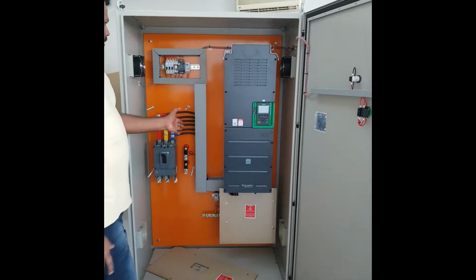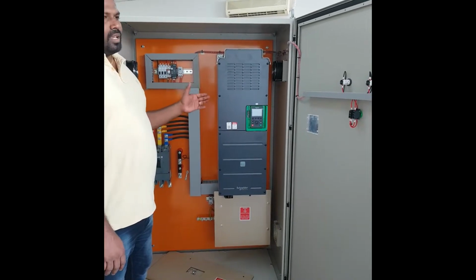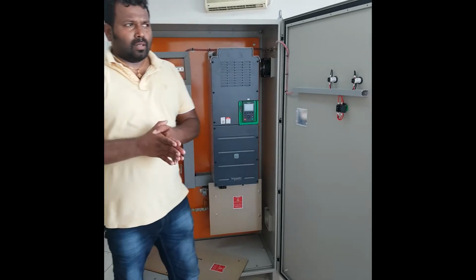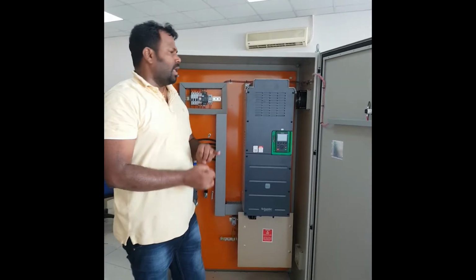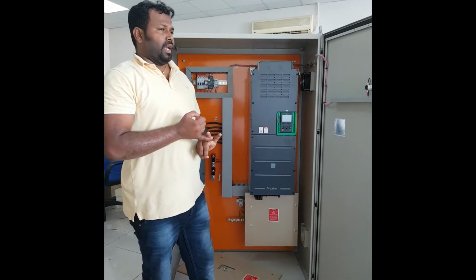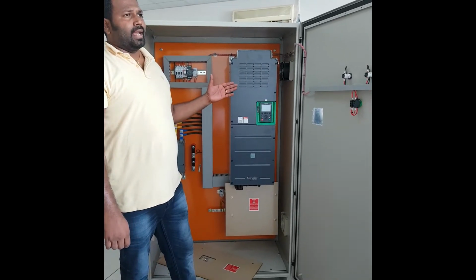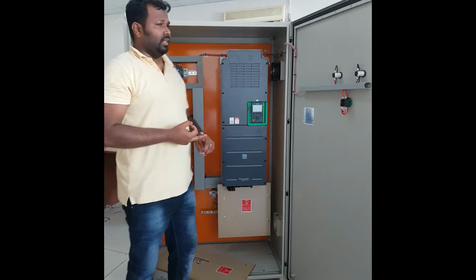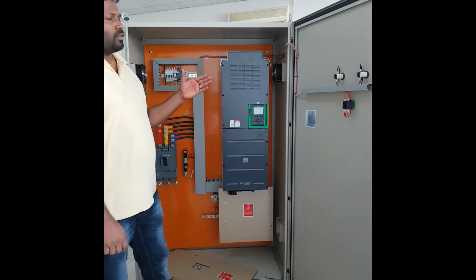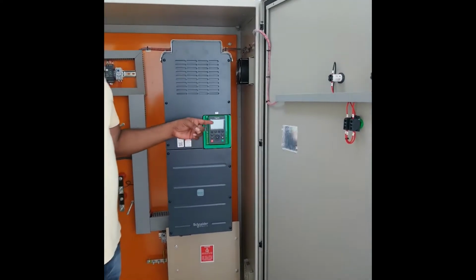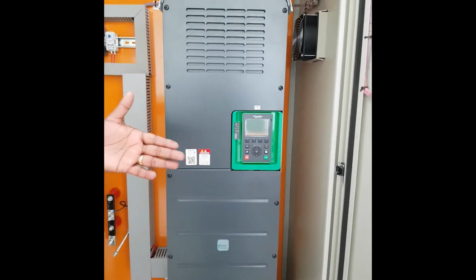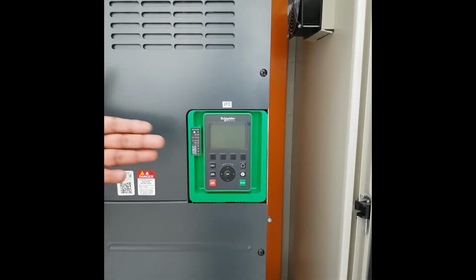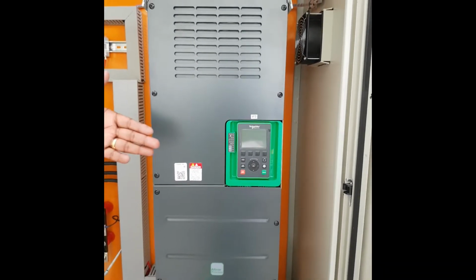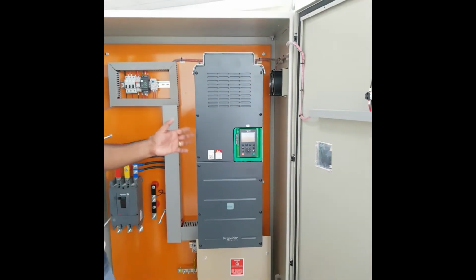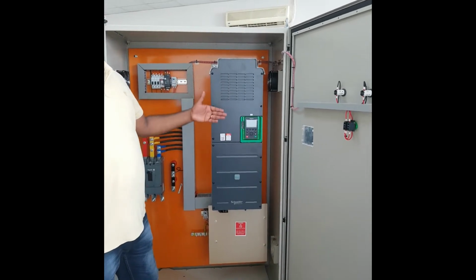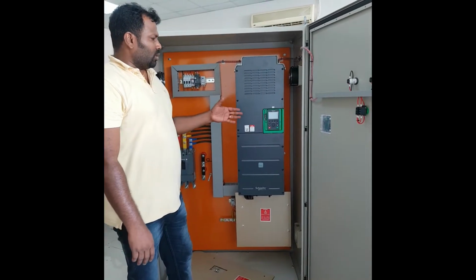Apart from this, the VFD, as I told you, has some inbuilt protections like under voltage, over voltage, over current and earth leakage protection. The VFD itself takes care of these basic protections. You have to set your nominal voltage, the voltage range, the low and over voltage limits, and your motor current in the VFD. Whenever there is any variation from your settings, the VFD will sense it and trip automatically. This VFD is fully equipped with printed circuit boards, and it is a programmable VFD.